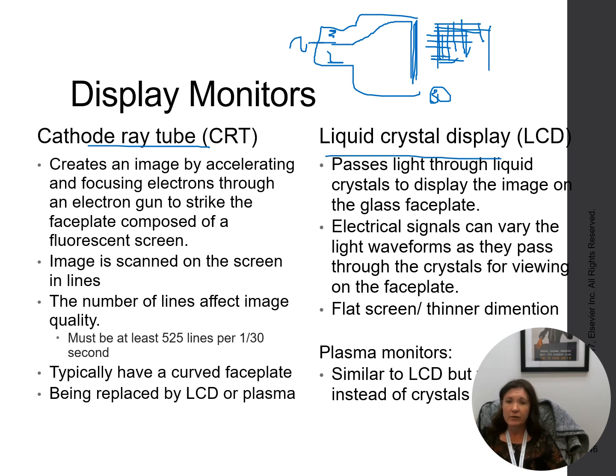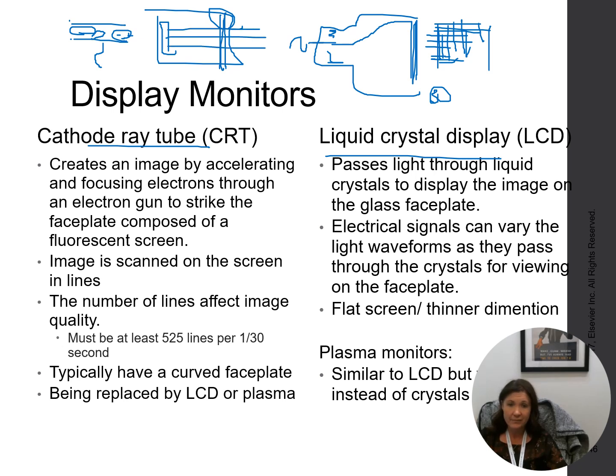Now we're typically using liquid crystal displays, and remember, we're looking at this from the side. This is my LED backlighting. Here is my TFT, and anterior to that TFT, we are going to have our sandwiched area. If I zoom in here, we have two diodes, and then we have liquid crystals with their dipolar charge, with a positive at one end and negative at the other. Depending on the charge that gets to my TFT, it's going to cause them to align and then allow this backlighting from the LED through.